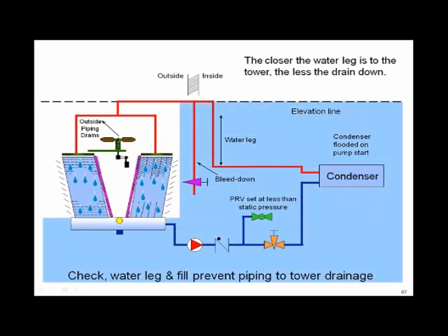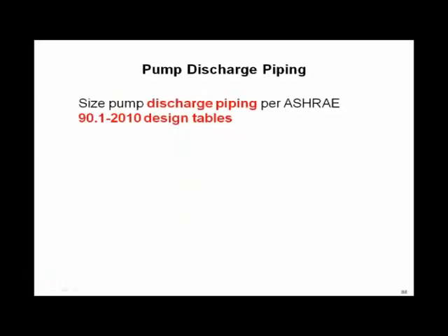I hope everybody sees where the water went. That water leg is trapping the water. So all the discharge piping, all the condenser water piping is full of water with the pump off. So how much water went into the tower? The water that went into the tower was in the hot decks of the tower, the fill of the tower, a little bit of overhead piping. But it was not enough to flood the tower. Everybody's happy because of the water leg. You turn the pump back on, you've got plenty of water to get everything going again, there's no problem.